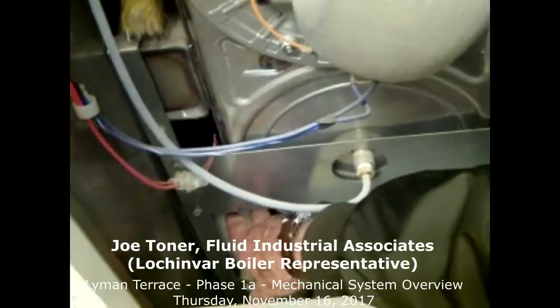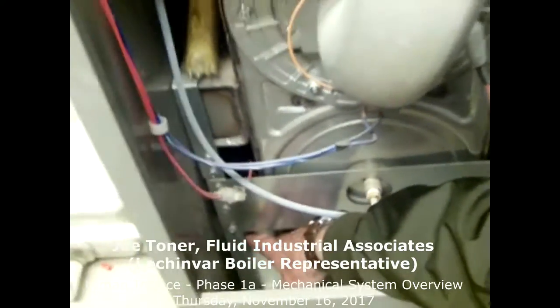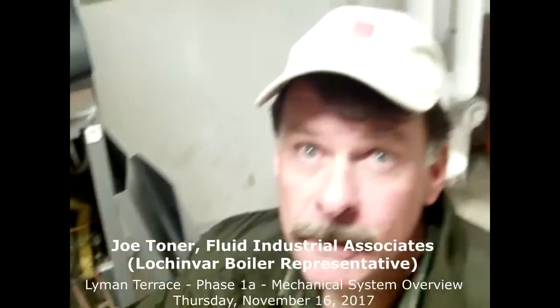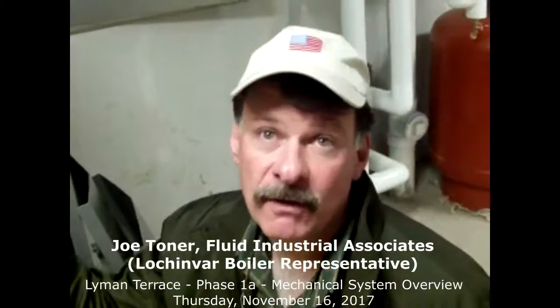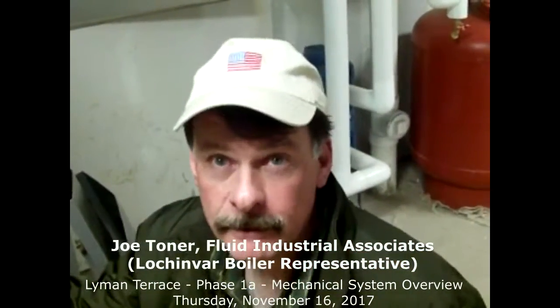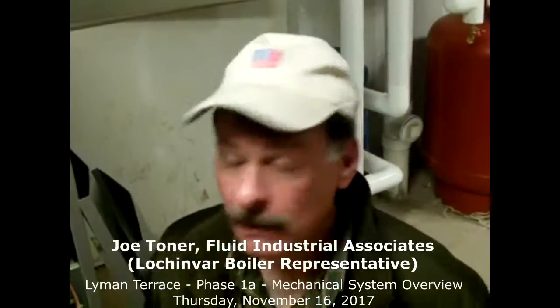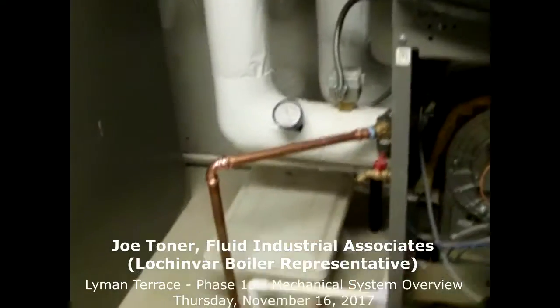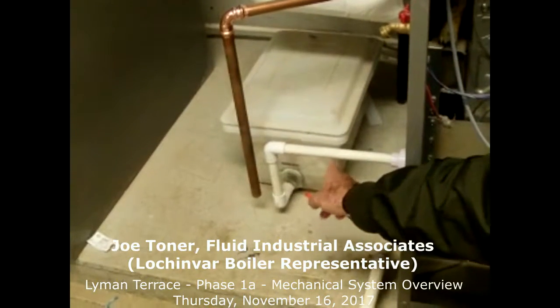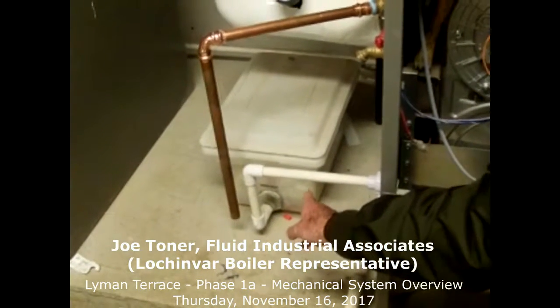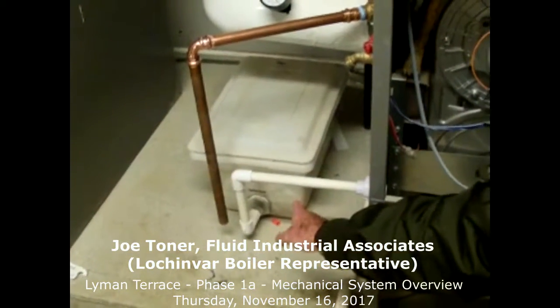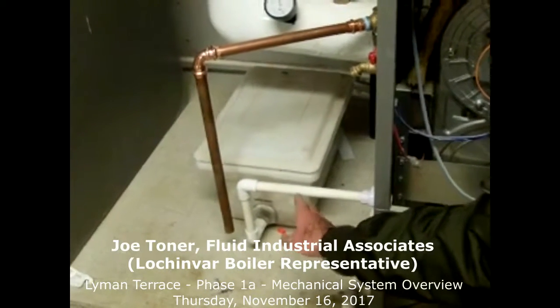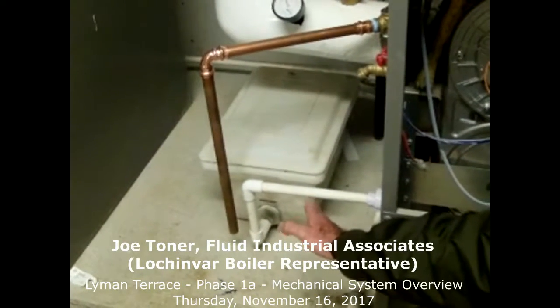There is a safety device on top that if this gets blocked, it trips a safety, and you'll get a message here that says condensate trap fault. So it's important to inspect that. It's also important to take a visual of this condensate neutralization kit. It's basically just limestone, which neutralizes the acidity of condensate, and over time those limestones will get eroded.